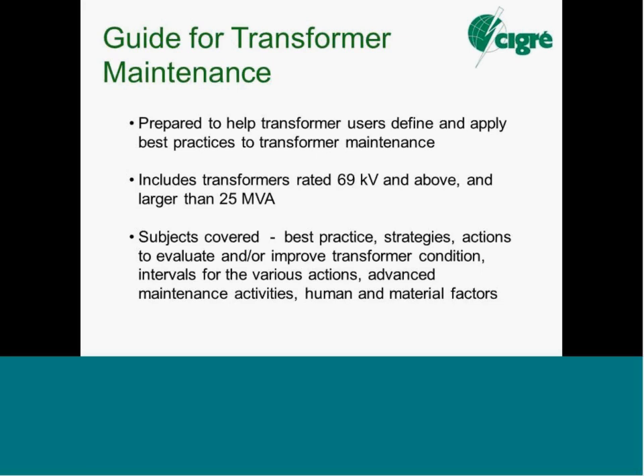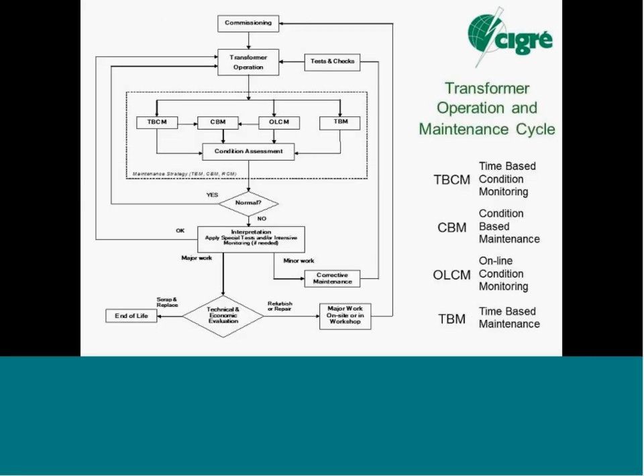So CIGRE in the A2 Study Committee, their charter is to look at power transformers rated 69 kV and above, larger than 25 MVA. So I put that there just to give you the relevance: this document is more for medium and large power transformers. Throughout the brochure you'll see very useful diagrams like this. And this diagram really tries to put into a flow chart what the transformer operation and maintenance cycle looks like.